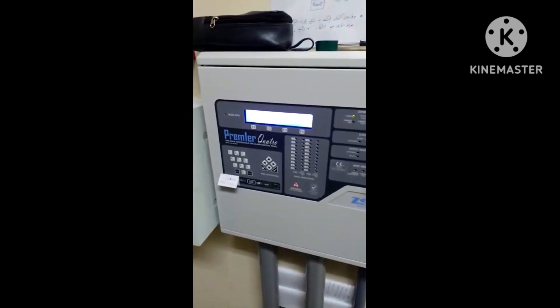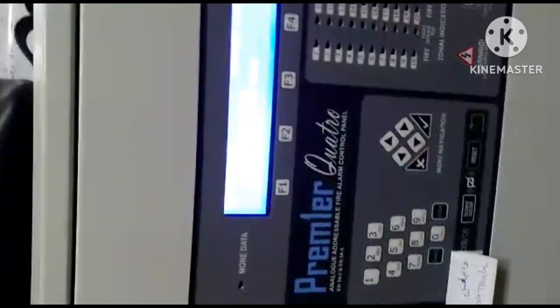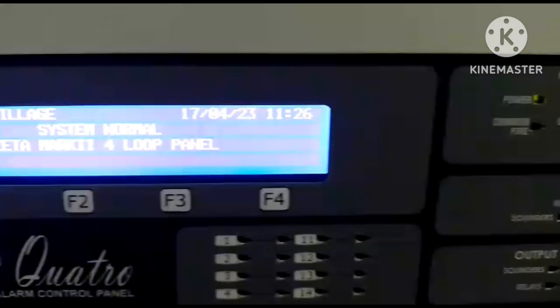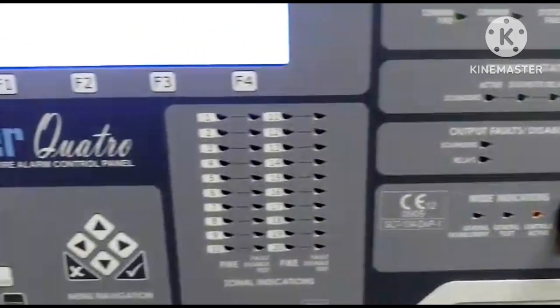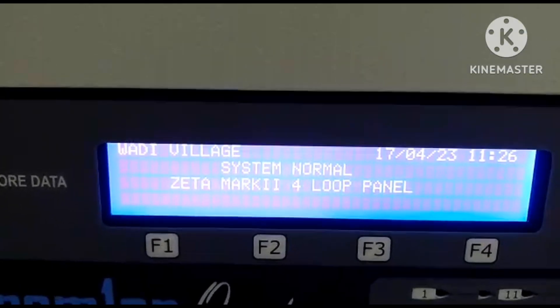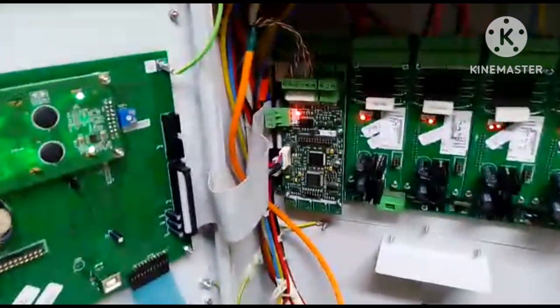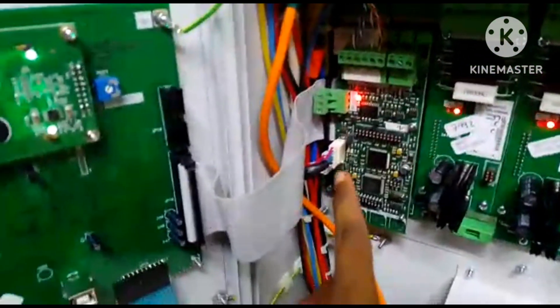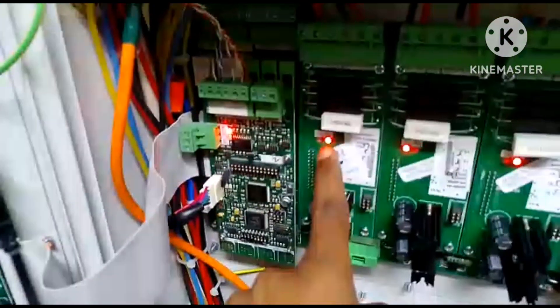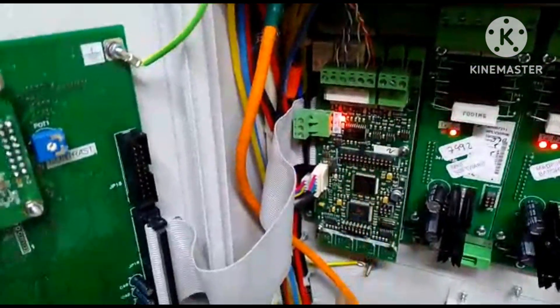This is a Wadi Village main panel. The panel is normal. Today's date is 17, time is 11:26, panel is normal. This is the network card we installed. The loop card will be blinking like this, but the network card will show only one red light. We installed a Cat6 cable — you can see it here.